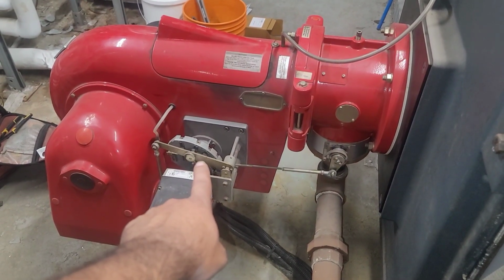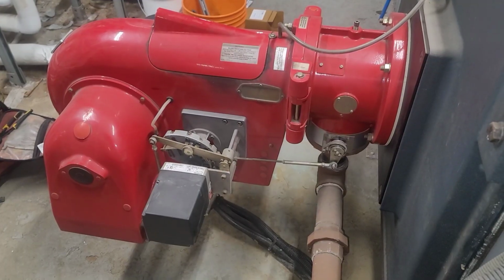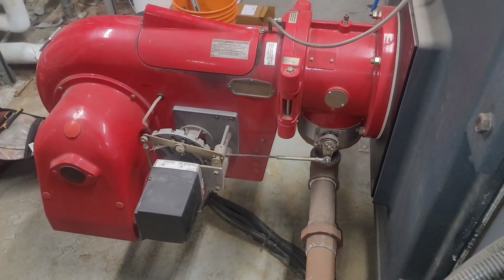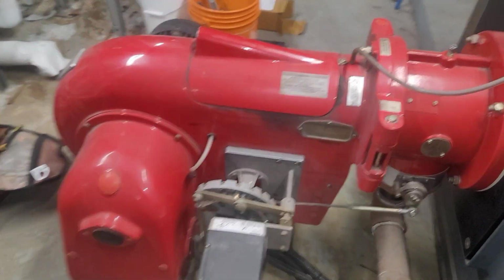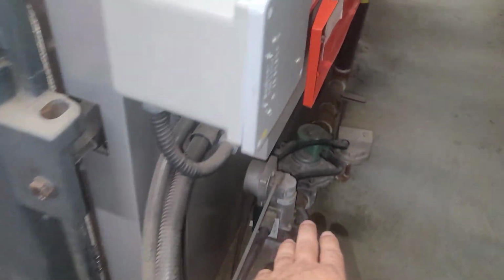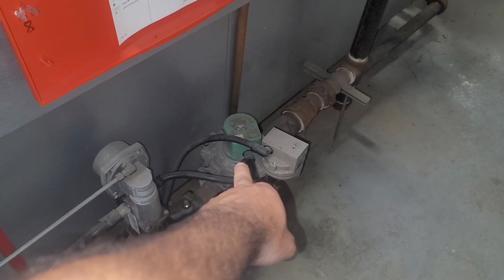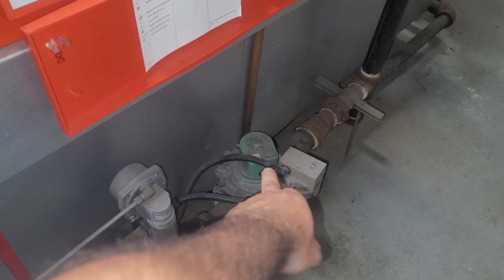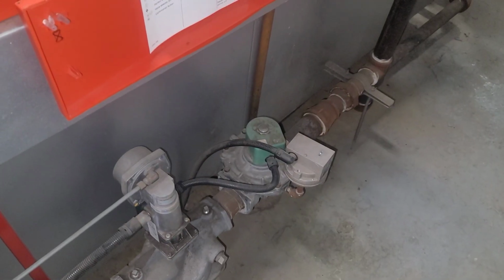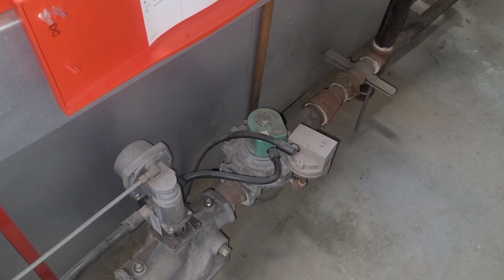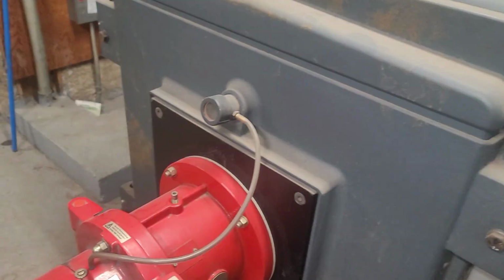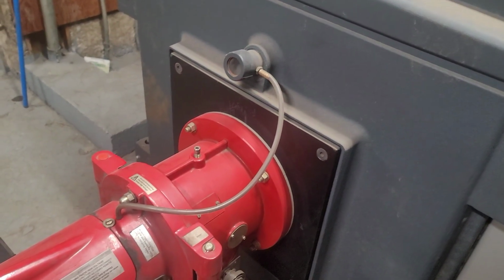Okay, now it's going back to low speed, and it will go for test fire, and we will hear this gas solenoid valve, and you will hear it soon. Yeah. So now the gas is okay. So it's fired. So we can see through here. It just started, and it will go on high fire.